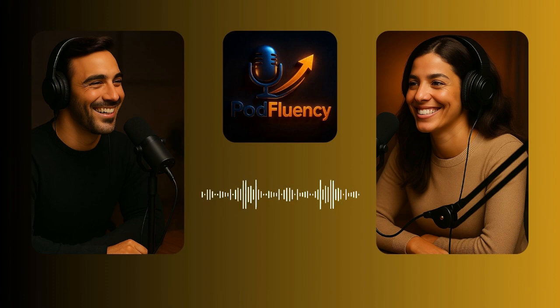Right. They're the voltage and current shifters, stepping up the voltage for efficient transmission and then stepping it back down for distribution and use. What are the main parts that make up a power transformer? Well, at the core, you've got windings, which are usually made of copper, and a core, which is typically made of laminated silicon steel. The windings carry the current and create the magnetic fields, and the core helps to guide the magnetic flux. These windings and the core are what we call the active part of the transformer.